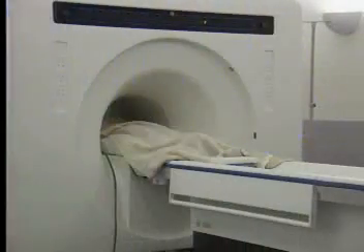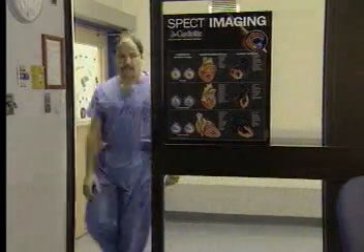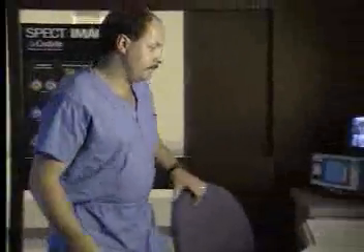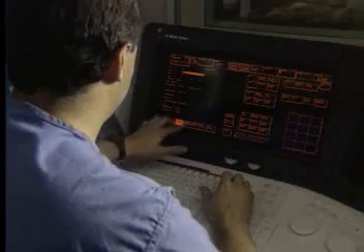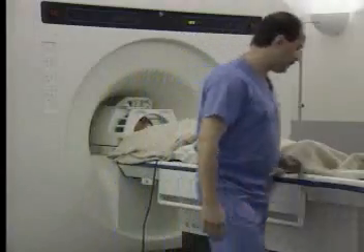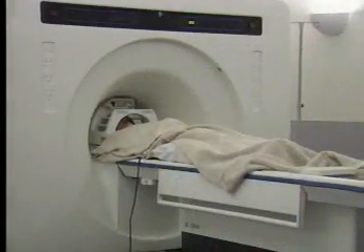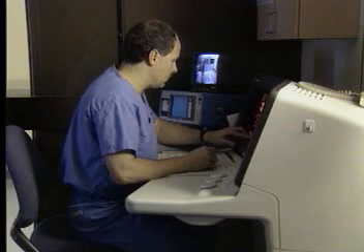A lot of people think of MRI as putting the body inside the scanner and us being able to take a picture of the whole body, but it doesn't quite work that way. Even though the whole body goes inside the tunnel, only a very small area can be imaged at once, and it's physically dependent on the size of the coil that you can use. The biggest coil is the body coil, which is inside the magnet itself, and it's 48 centimeters long.